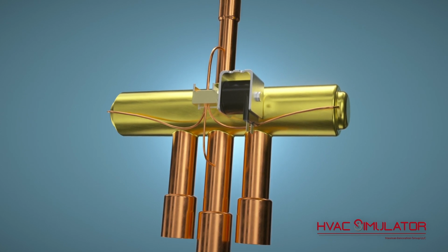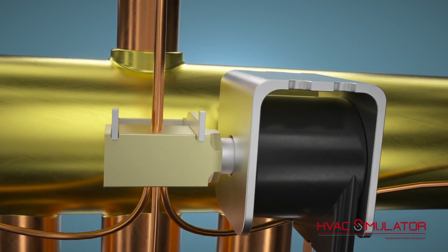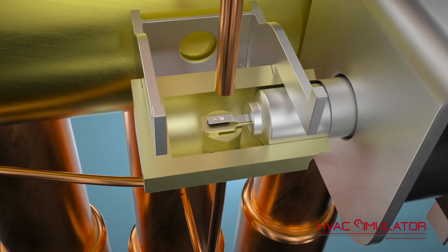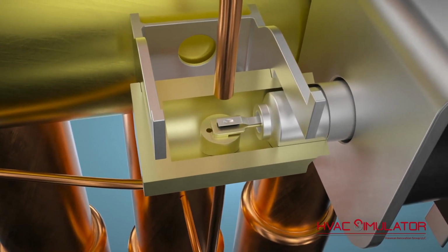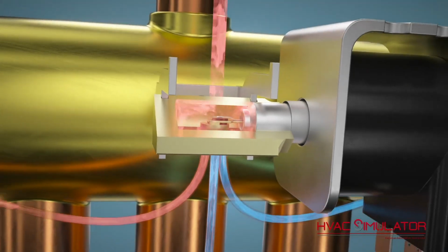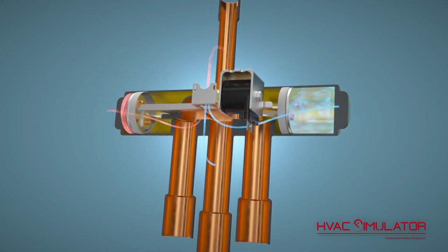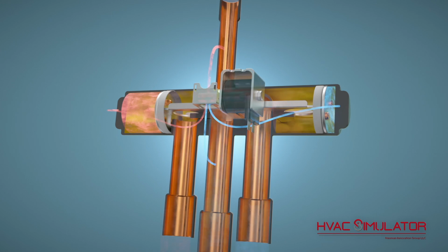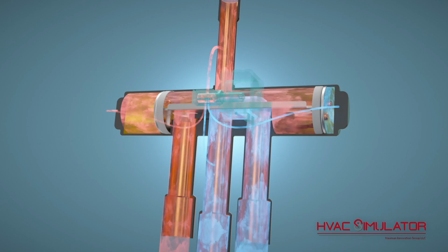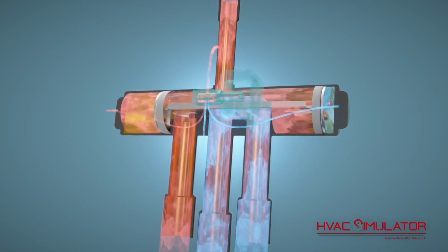When the system switches between heating and cooling, the thermostat sends a signal to energize the solenoid coil and generates a magnetic field. This magnetic field exerts a force on the core, causing a mechanical motion. The core and stem move, causing the pressures to change in the 2 outer capillary tubes. The high pressure in the capillary tube is now directed to the other side of the valve body, causing a mechanical motion of the slider mechanism and directing hot gas to the outdoor unit. The refrigerant on the other side of the valve body depressurizes and flows back to the pilot assembly through the stem gasket and back to the low pressure suction line.